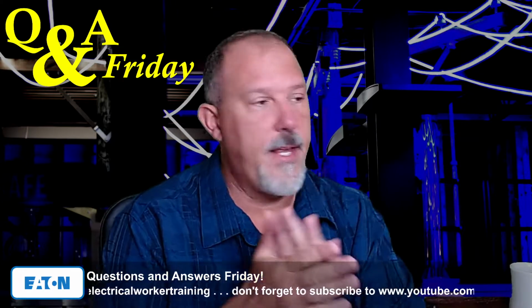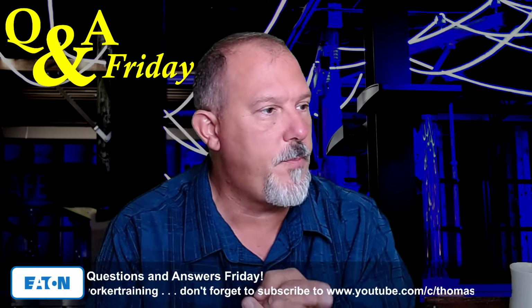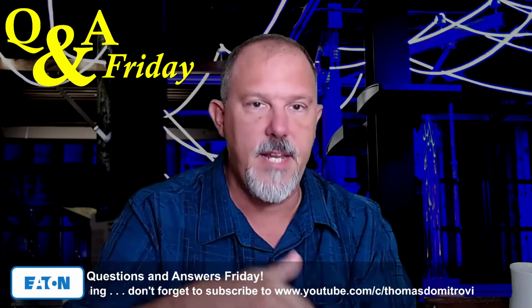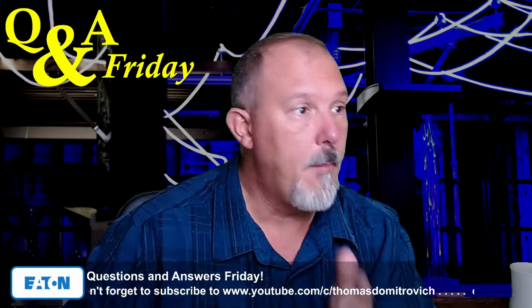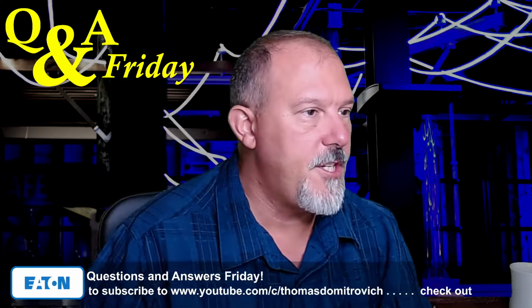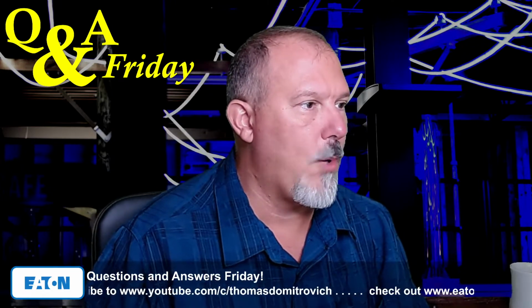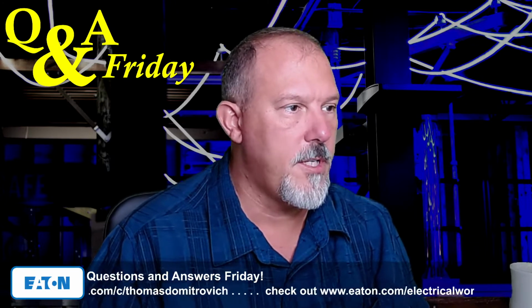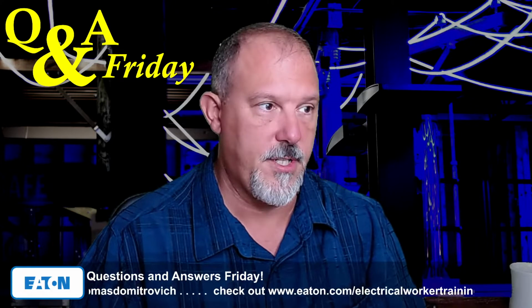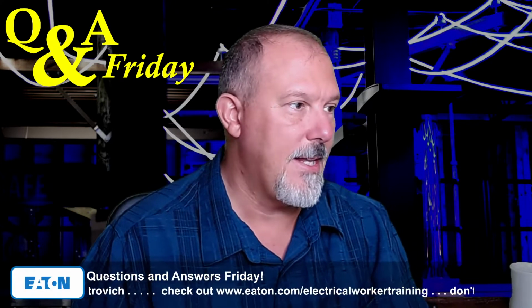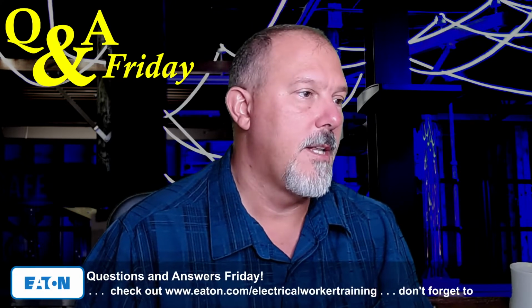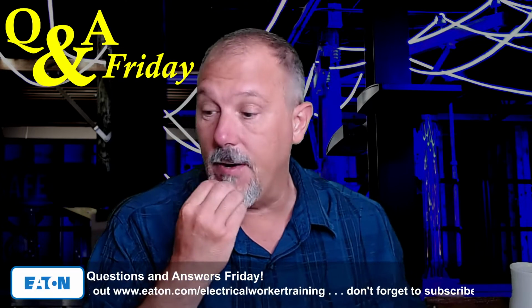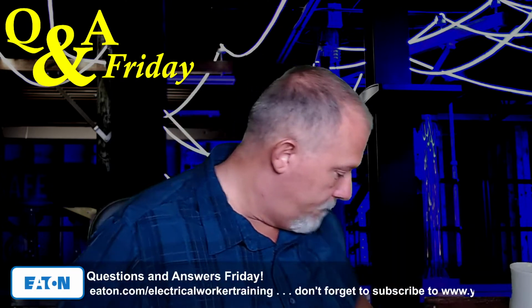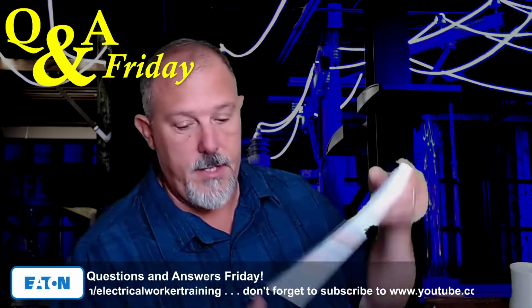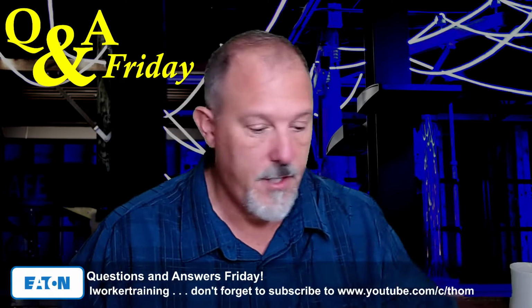JW said, it is less likely you would be working on energized medium voltage equipment, but the definition of de-energized is quite different in that you have to ground it and have all the concerns about induced voltages, static from T lines, or contact with other lines somewhere up or downstream. All right, JW, thanks for the note.